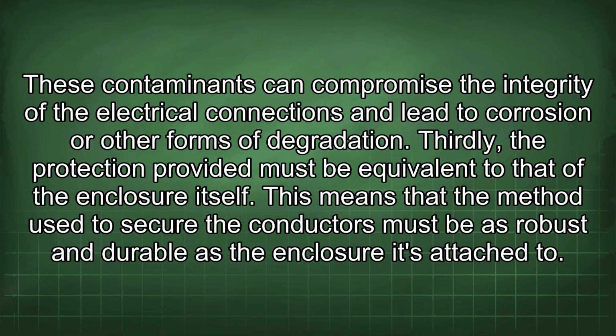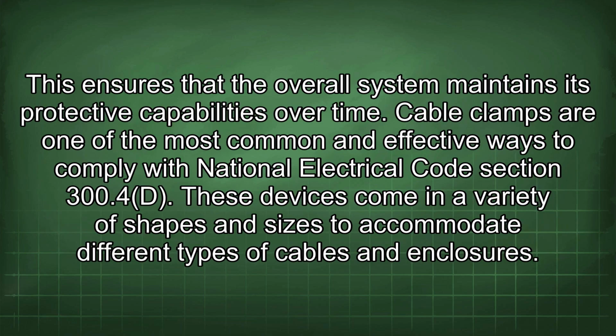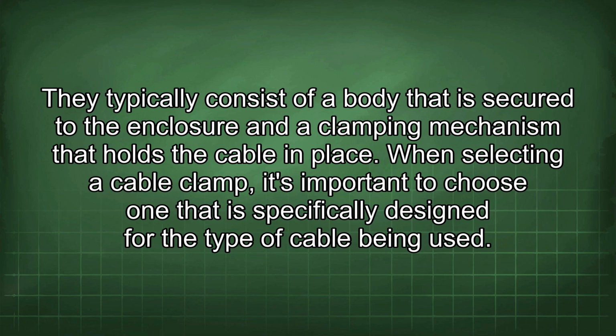Thirdly, the protection provided must be equivalent to that of the enclosure itself. This means that the method used to secure the conductors must be as robust and durable as the enclosure it's attached to. This ensures that the overall system maintains its protective capabilities over time. Cable clamps are one of the most common and effective ways to comply with National Electrical Code Section 300.4D. These devices come in a variety of shapes and sizes to accommodate different types of cables and enclosures.